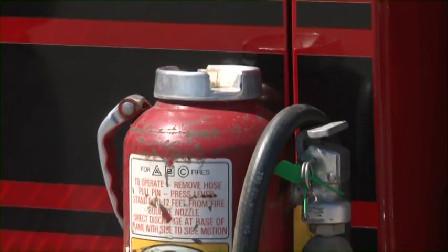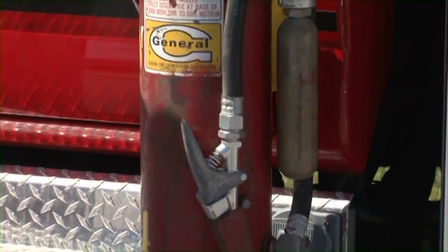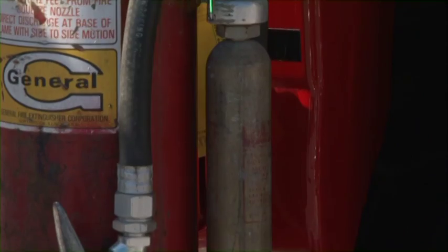So why aren't all extinguishers just stored pressure units? Well, they all have a purpose. For instance, you'd find many cartridge-operated extinguishers being used in industrial facilities. Because they contain the expellant gas in a separate cartridge from the extinguishing agent, it makes them much easier to reload, allowing an operator to discharge a unit, get it recharged, and return to the fire in a reasonable amount of time.